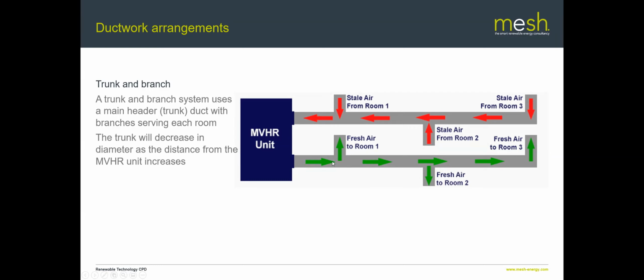Obviously, as you get further away from the MVHR unit, the diameter of that trunk will reduce, and the size of the branches off to each room will depend upon what the air supply requirement is to that particular room.